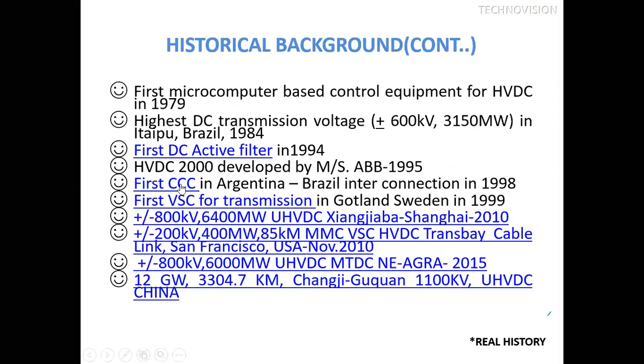Then the first triple C HVDC. This technology is based on thyristors, but the specialty of this first triple C HVDC was that between the thyristor valves and converter transformers, they used series capacitors, so that if there is a passive network, suppose generation is low on any bus, you can connect with this technology. Whenever the short circuit ratio is less than 3 also, you can connect your HVDC system with this triple C HVDC. Then the first voltage source converter based transmission was developed in Gotland, Sweden in 1999.